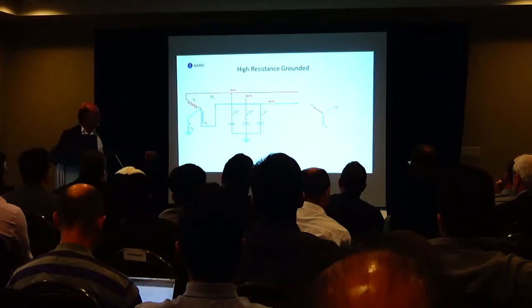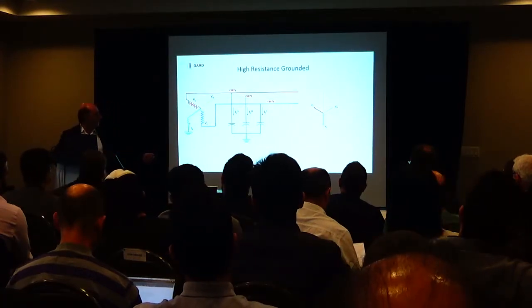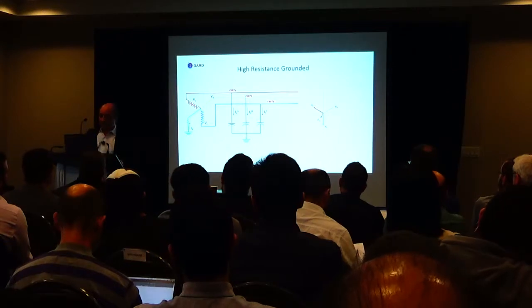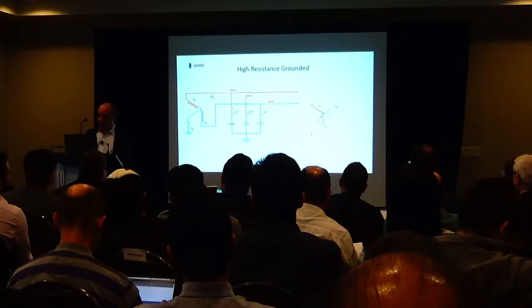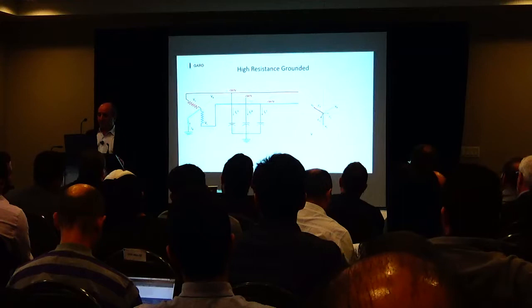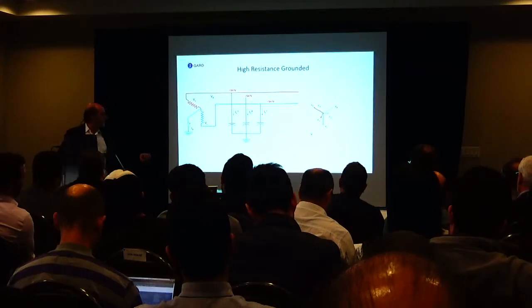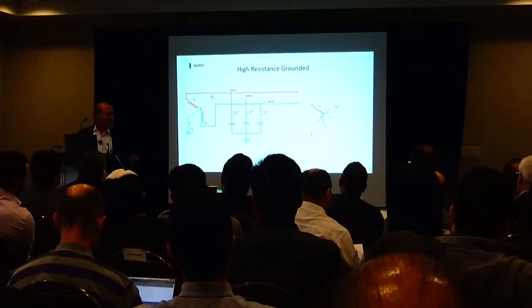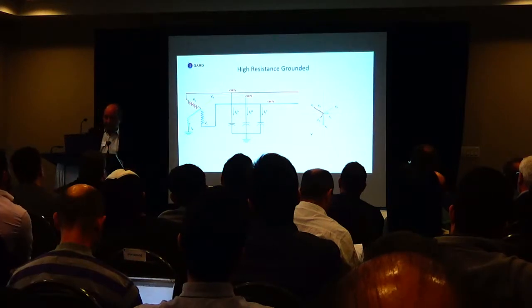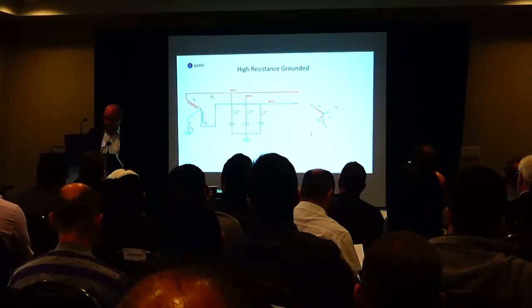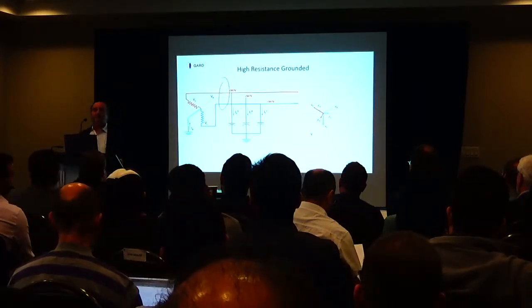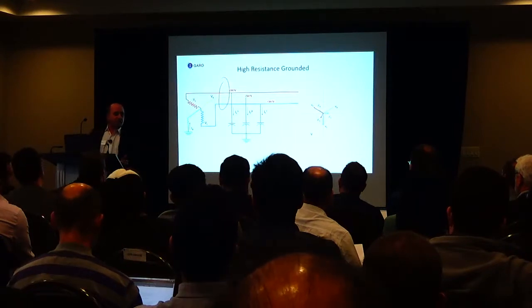So this is what happens with your voltages. 347 volts phase to ground, and there's your capacitance, and they sum up to 0, because the capacitance going there, there, and there add up to 0. That means if you put a zero sequence CT right here, even if you have a fault, you're going to measure 0.